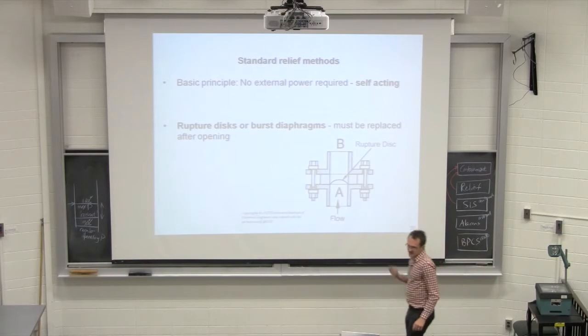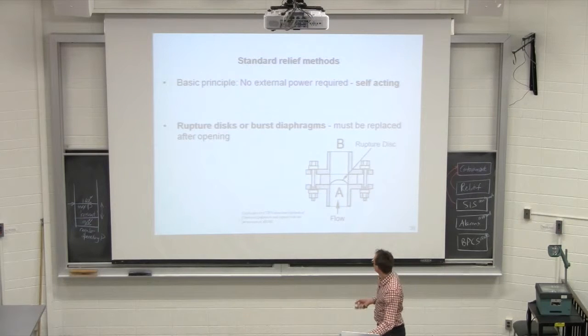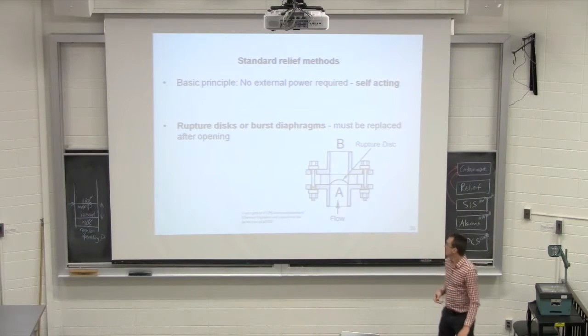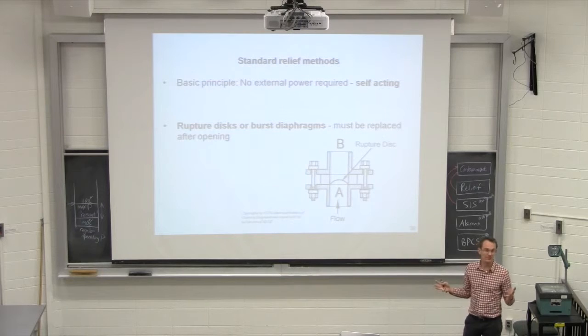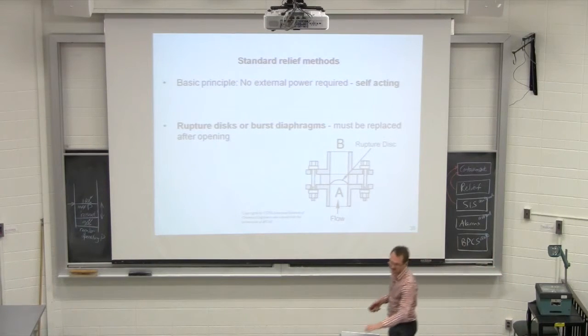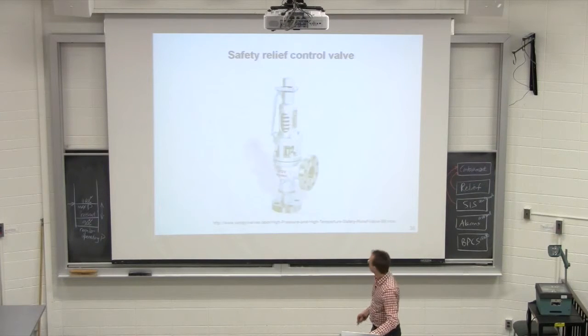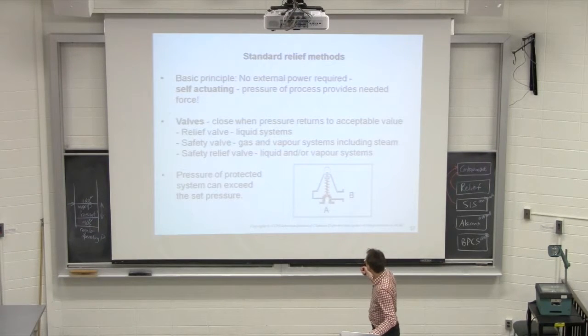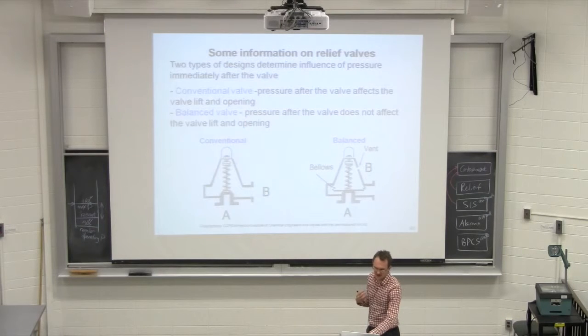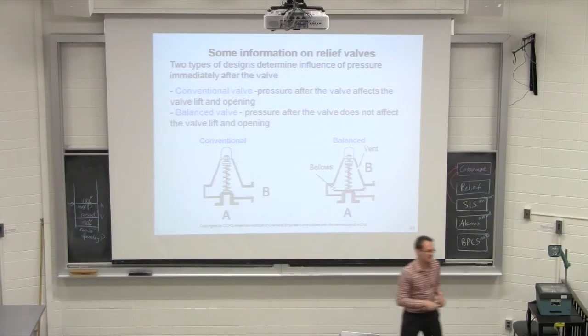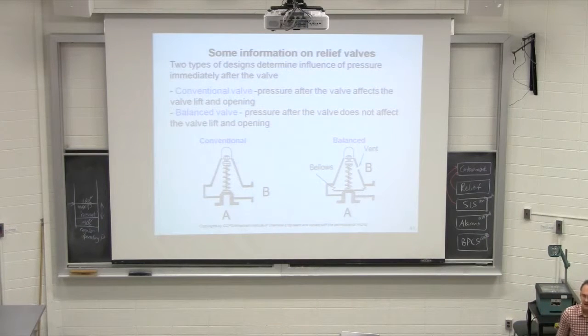Okay, and today this rupture disc opens when that pressure is exceeded beyond the safe level it can take. Now you've got a permanent opening in your pressure vessel. Unlike the relief valve, once the pressure inside your tank is back to its safe operating point, that valve will reseat. So why do we have these two types? We'll look at their different advantages in a minute.